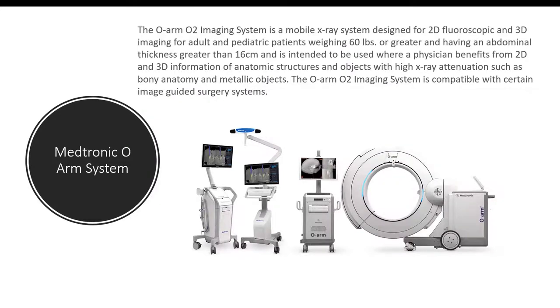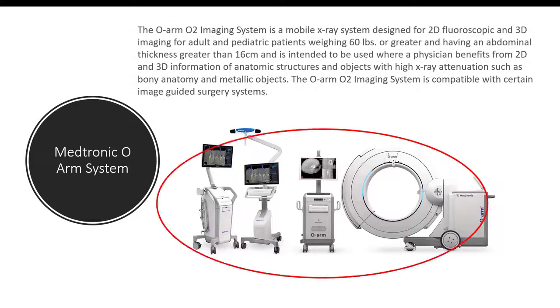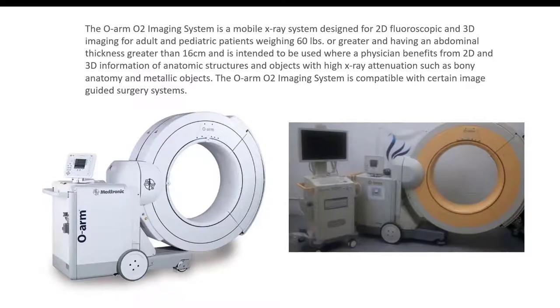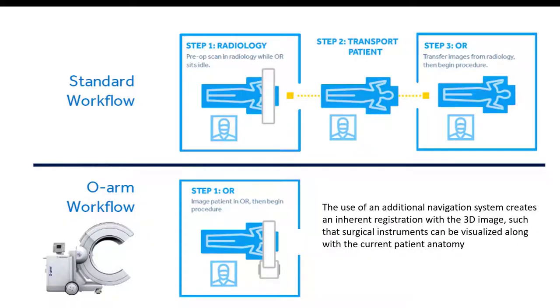Another configuration that uses 3D CT cone beam and fluoroscopy is the Medtronic O-Arm system. The O-Arm has limited functionality and is used only in surgery, whereas the fluoroscopic C-arm can be used anywhere. This system creates 3D images that are stored in the computer's navigation system and serve as templates for real-time fluoroscopy during surgery. The O-Arm is mobile and can be moved out of position after images are acquired.